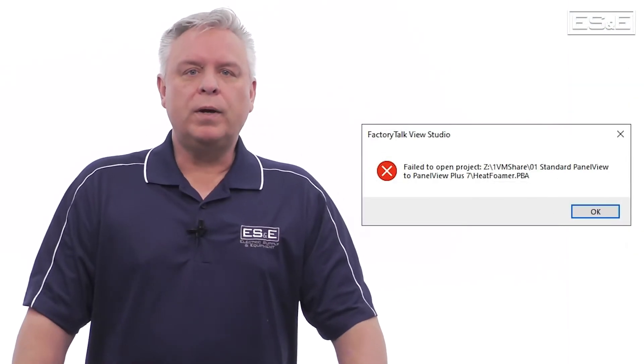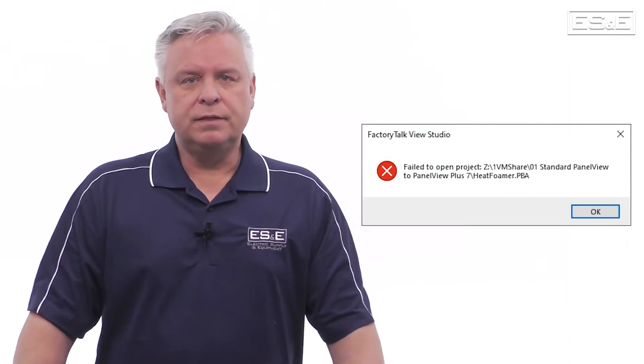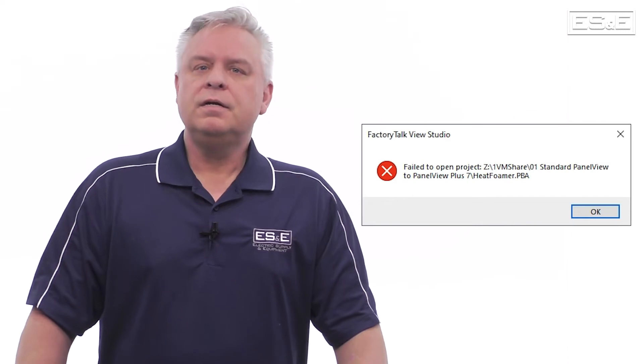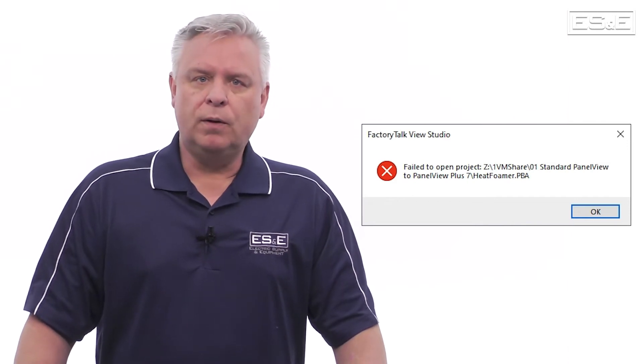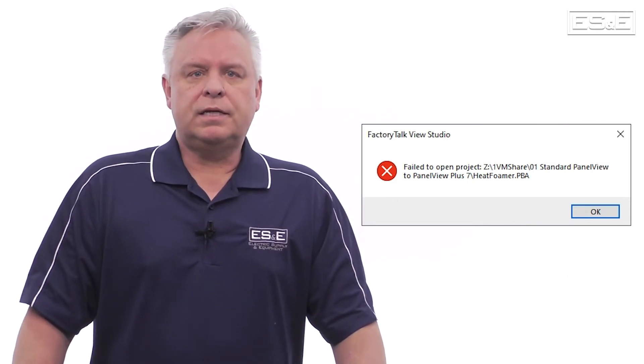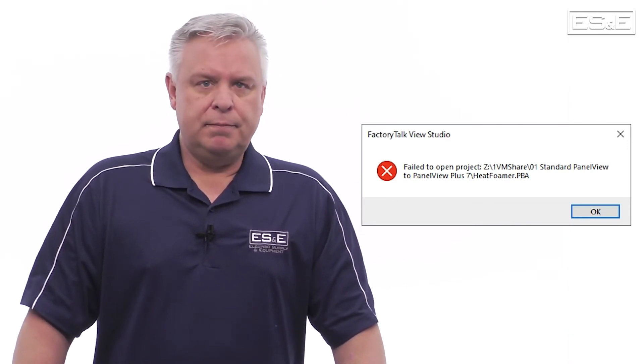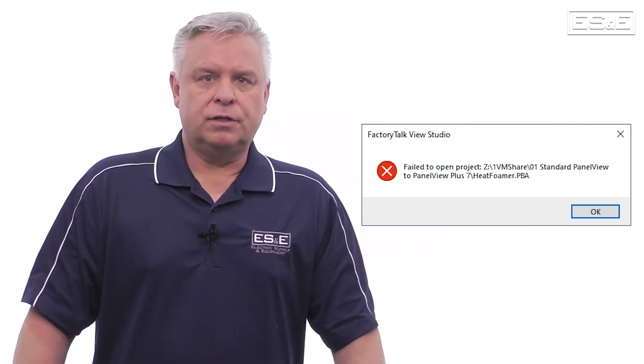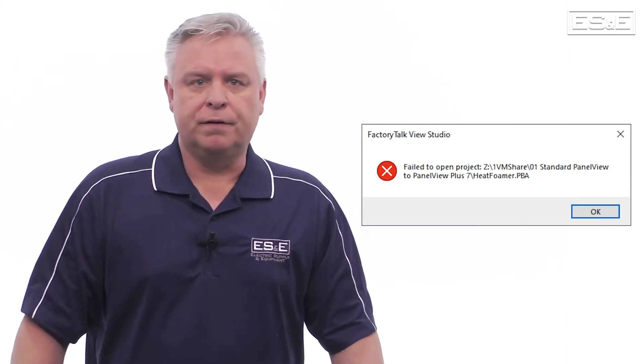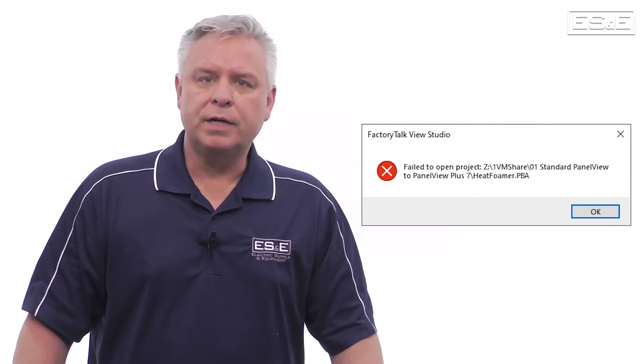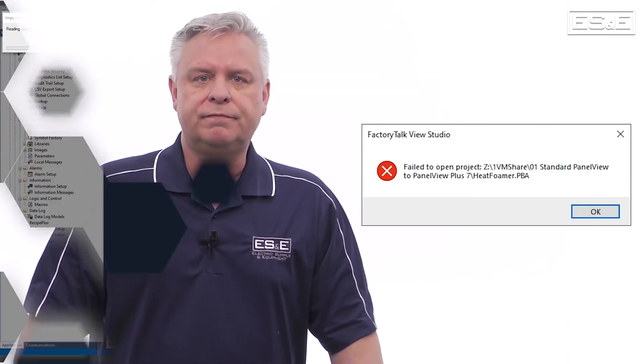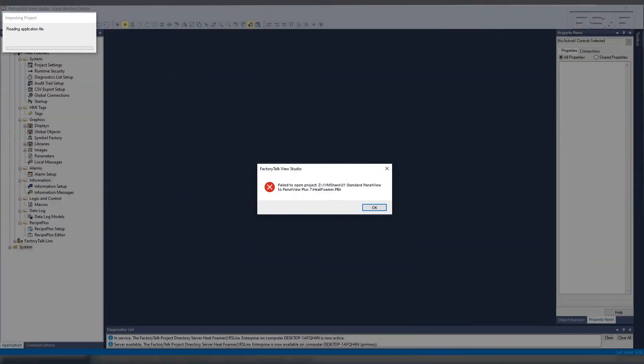The other thing I'll point out is if you get a 'Fail to Open Project' error during the import, you need to copy your .pba file to the local drive instead of trying to open it from a mapped or external drive. This error could also happen if you have the file open in Panel Builder 32 while trying to do the import.